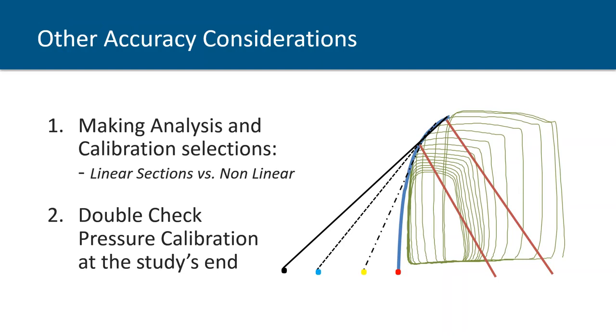And similarly, for example, if you're assessing tau, a time constant of relaxation, which is a mono-exponential fit, if you look at your raw data points collected from the aortic valve closure to some value above end diastolic pressure, that curve needs to be mono-exponential. Otherwise, you introduce enormous amounts of variation. And there's a really great paper by Burkhoff, Mirsky, and Suga, going over some of the analysis techniques. So it's important that when you go through the trouble of calibrating, you apply the appropriate techniques so that you reduce your variability as much as possible.